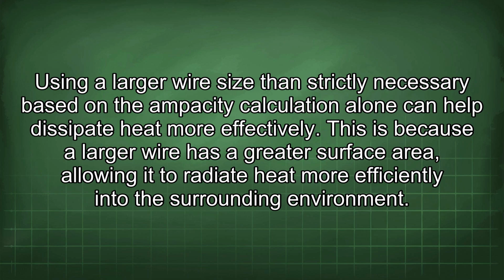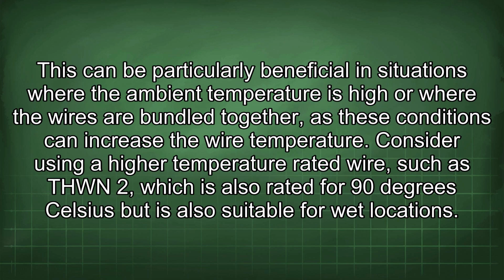Using a larger wire size than strictly necessary based on the ampacity calculation alone can help dissipate heat more effectively. This is because a larger wire has a greater surface area, allowing it to radiate heat more efficiently into the surrounding environment. This can be particularly beneficial in situations where the ambient temperature is high or where the wires are bundled together, as these conditions can increase the wire temperature. Consider using a high temperature rated wire such as THWN-2, which is also rated for 90 degrees Celsius but is also suitable for wet locations.